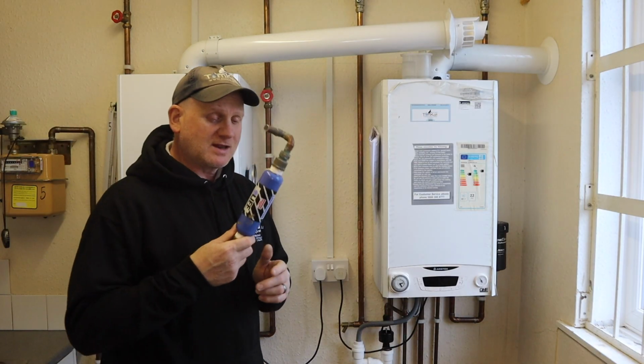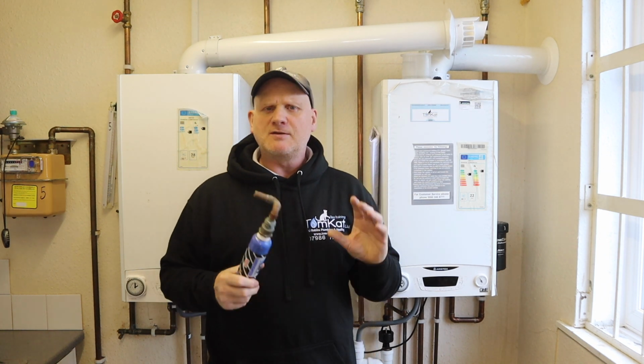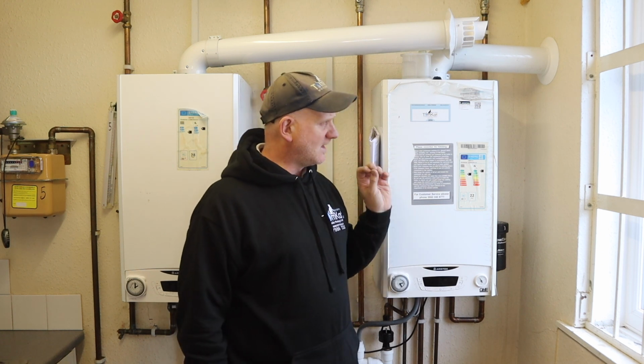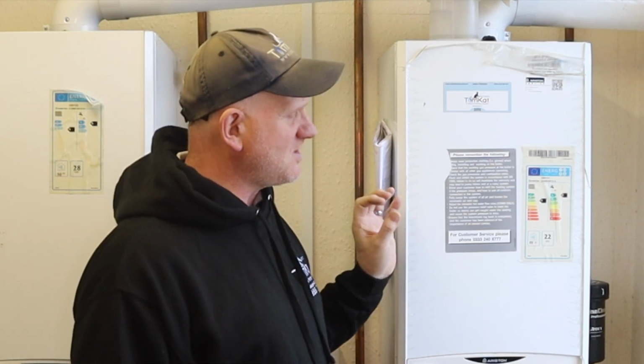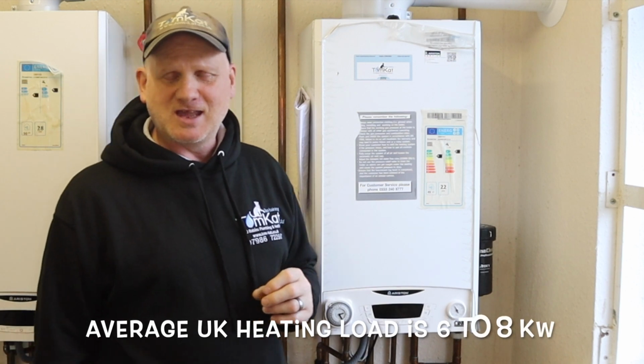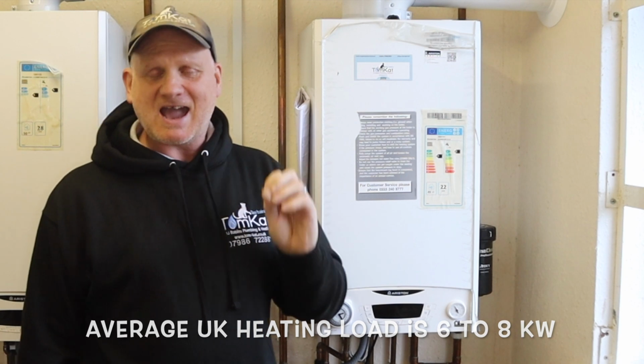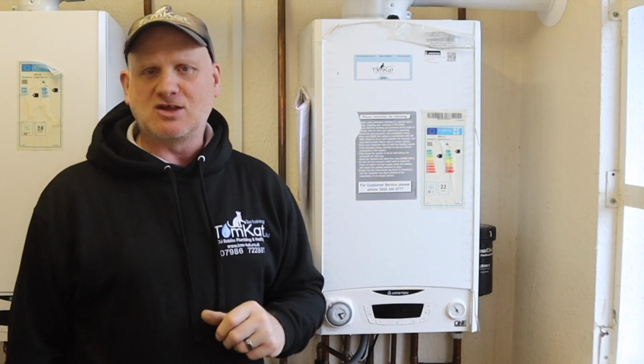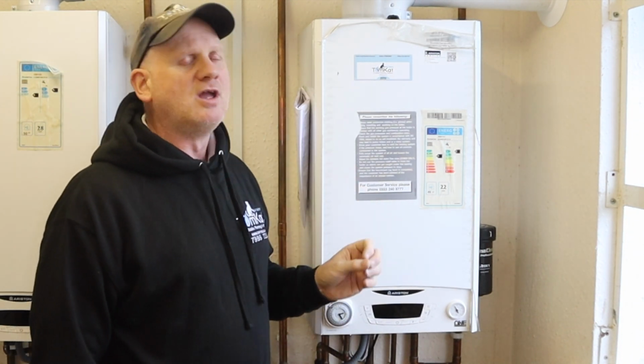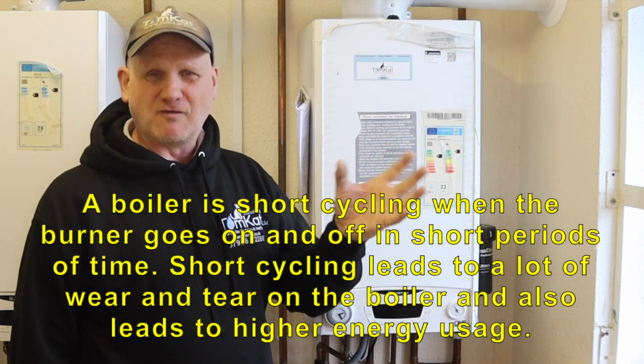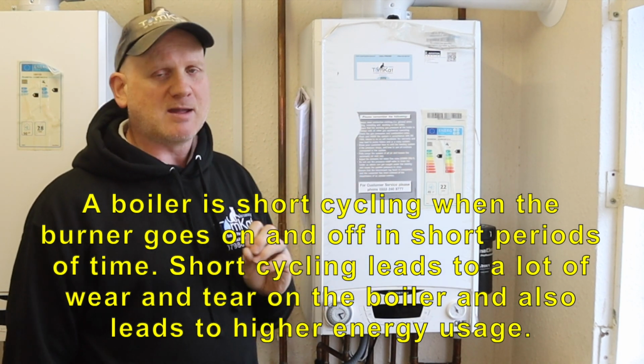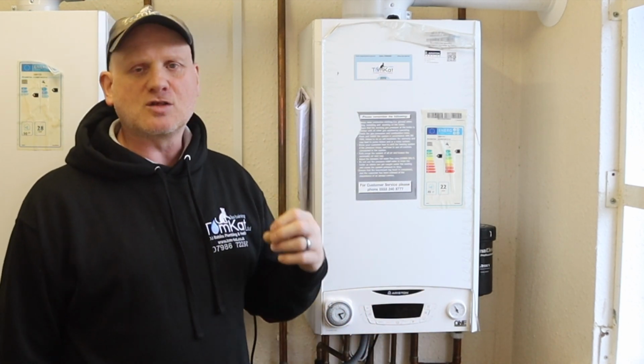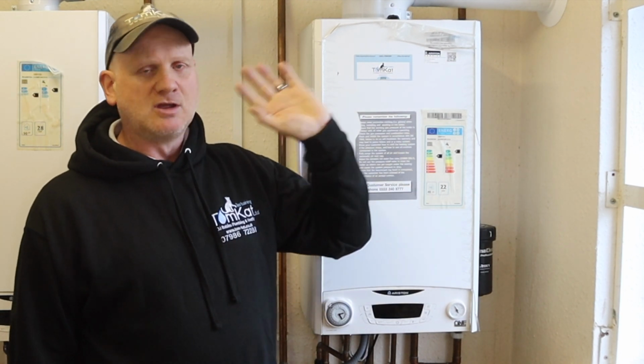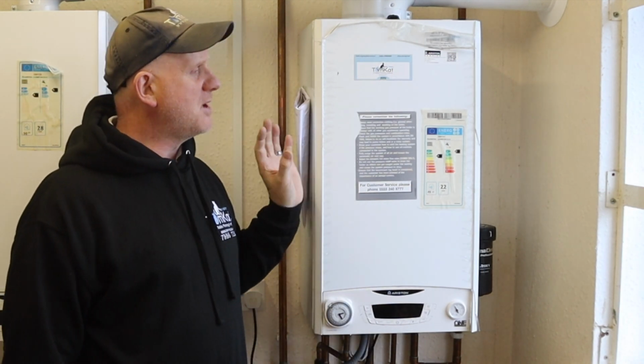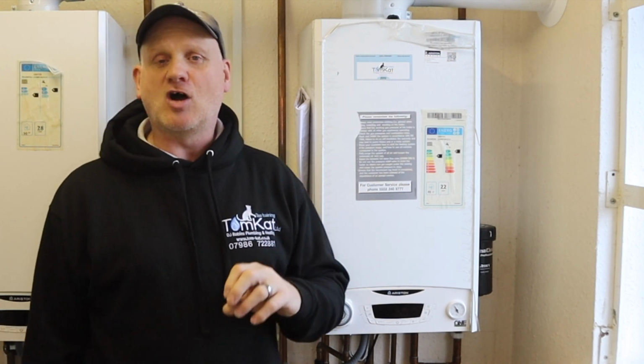As well as little things like this prolonging the life of your boiler, there are some simple things we can do to make these boilers last even longer. And that is actually getting them sized correctly and set up correctly for the house they're installed in. If we've got a 30 kilowatt boiler, we might not need 30 kilowatts for central heating. So this boiler could be range rated down to the kilowatts required for the house. So a simple heat loss calculation by an engineer would be able to allow them to range rate this down, which will cut down on boiler cycling. That means the boiler going on, off, on, off, on, off all the time, and allow the boiler to run at a lower temperature. Things like weather compensation as well will also help this by automatically reducing the flow temperature dependent upon what the temperature is outside. So actually making the boiler work less will prolong the life of your boiler.